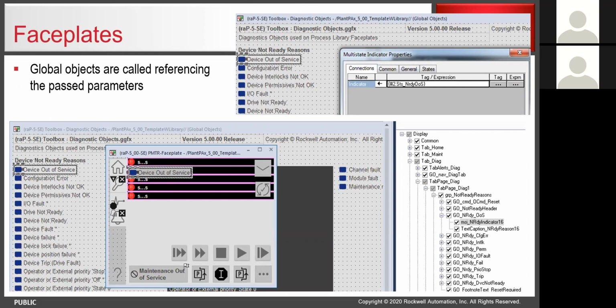Alarming and stuff like that is obviously different, but that's not typically something on the faceplate. On the faceplate, we're typically doing more of a Boolean, tag-based alarming from the controller, where we're using tag values to illuminate that there is something wrong, and then in parallel the alarm and events function is grabbing that same value and looking at it.